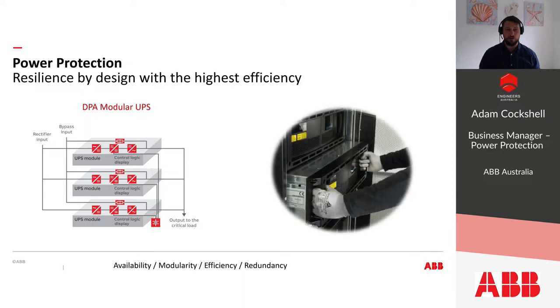ABB's DPA modular UPS range is designed to make sure that power is always available when you need it. Each high reliability standardized module is self-contained, fast to service and maintained with short MTTR, that is mean time to repair, thanks to the online swappability of the modules, front serviceability and smart design. It takes less than 10 minutes to replace a module, so nothing needs to ever be switched off. And if you ensure the commonality of DPA modules across your site, you ensure an ease of spare parts and obviously the ease of maintenance.